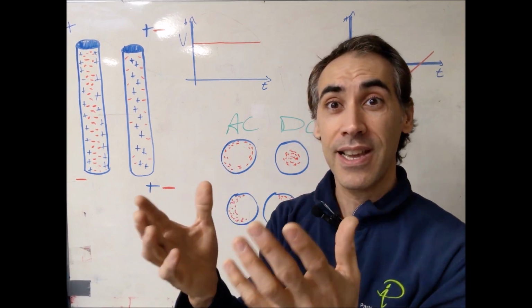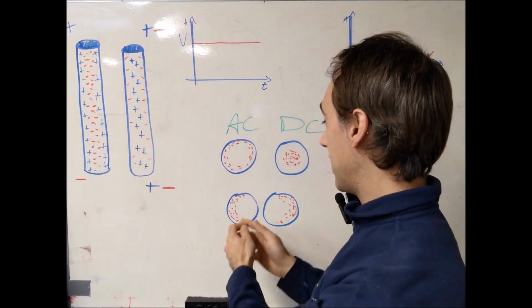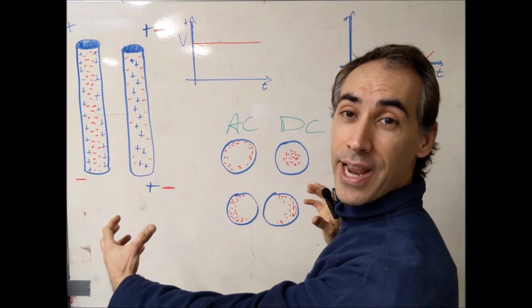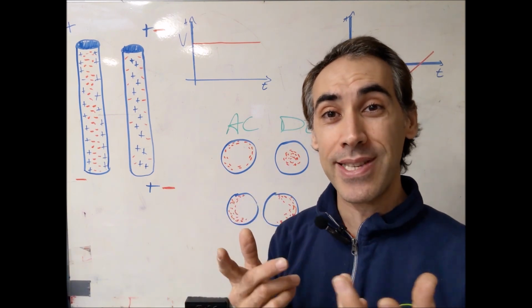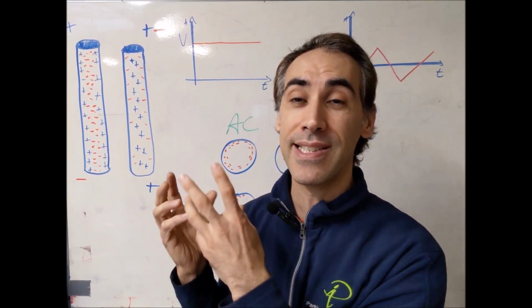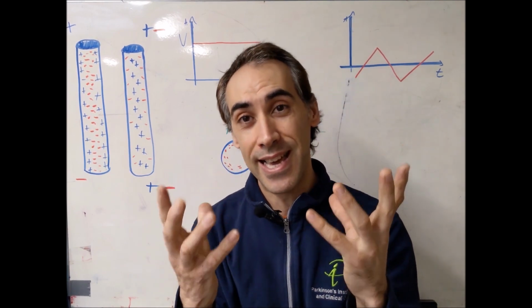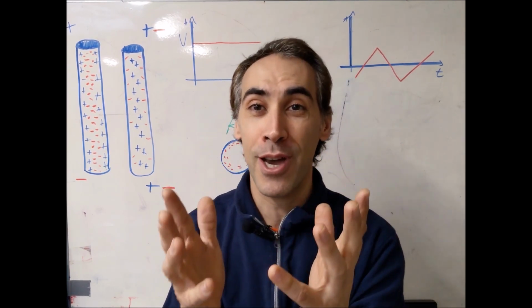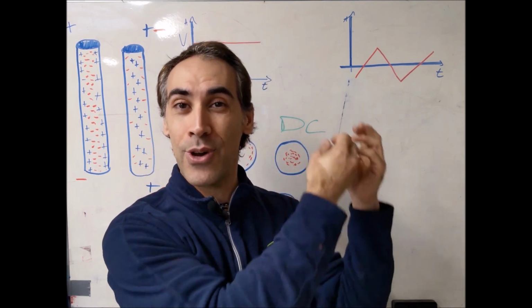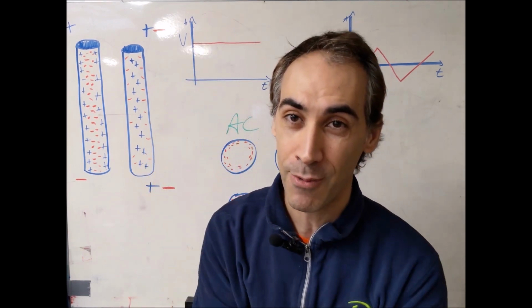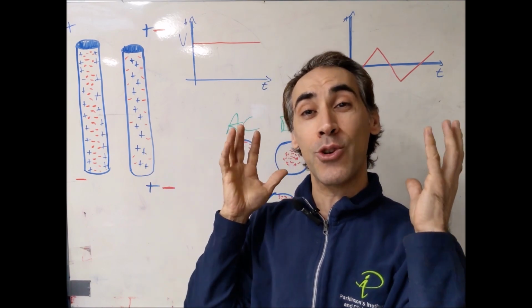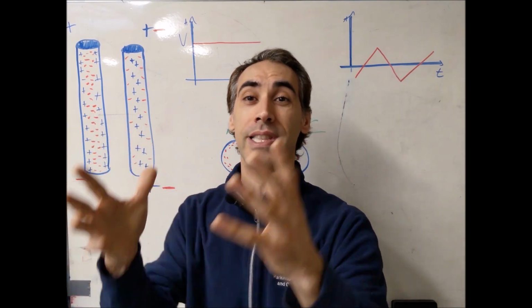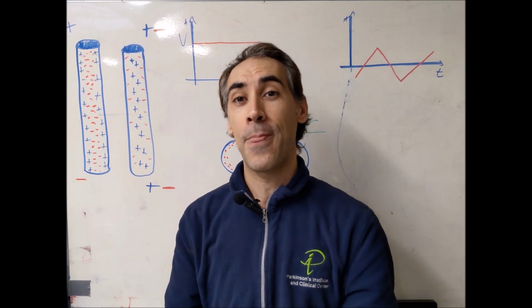Yes, because they are carrying the same currents. Now, the charges prefer to spread apart, as you can see. And once again, yes, they can cause this cable to heat up. We do not size our cable to our waveform. We size our cable according to how much charge wants to travel through the conductor. That's what we call current.